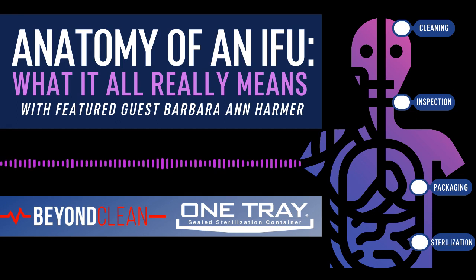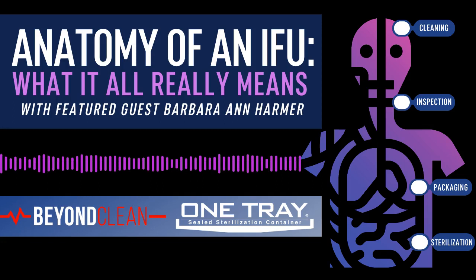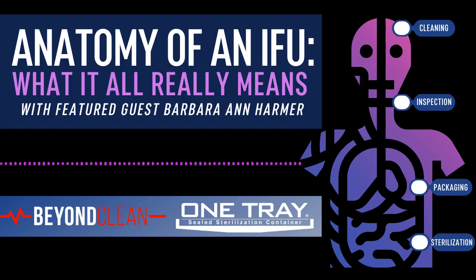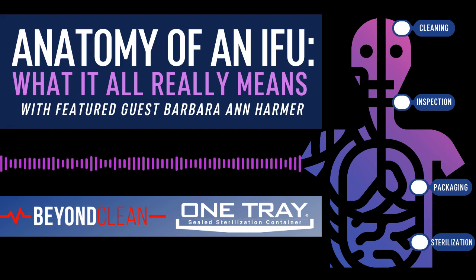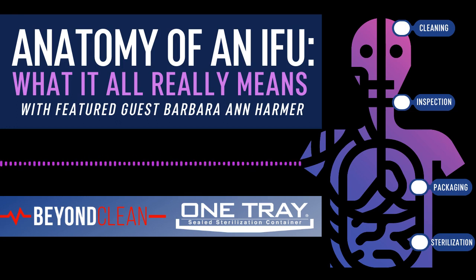So let me throw out there an example very quickly of how immediacy could be defined by your organization. Your adoption of this term immediacy could be that immediacy is recognized when a sterilization process involves the use of a packaging system that cannot be stored for future use. If the sterile barrier system, rigid container, peel pack, and/or wrap does not have the capability of being stored for future use, the record will be documented as an IUSS cycle. So again, to be brief with this, if your organization says, unless we use an FDA cleared packaging system for immediate use steam sterilization, key factor, no storage, that is our definition of what we call immediacy.